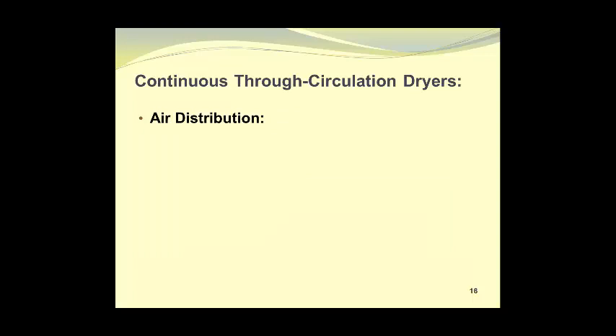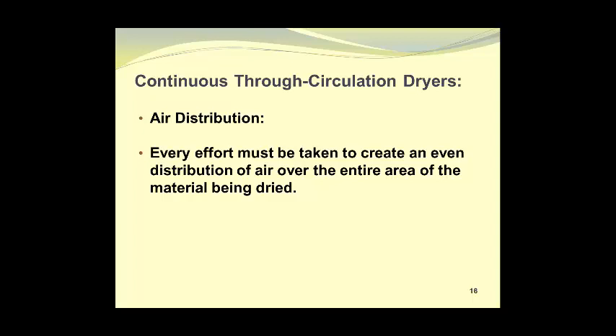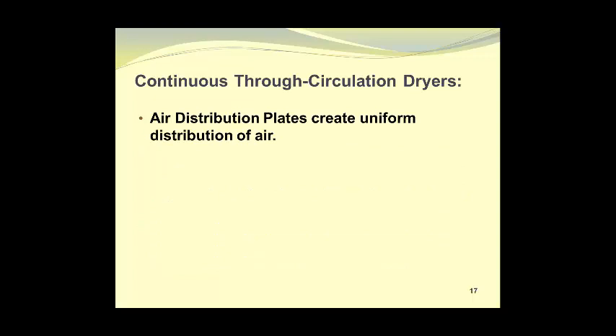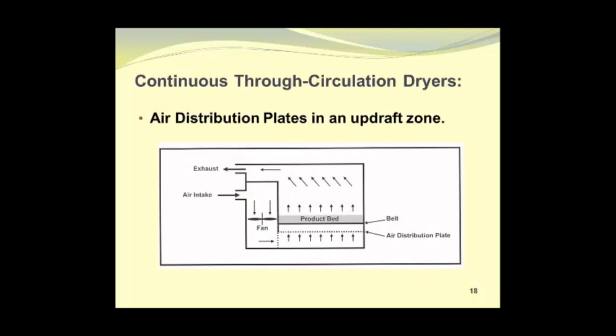Air distribution is an important factor. Every effort must be taken to create an even distribution of air over the entire area of the material being dried. Uneven distribution of air creates a lack of uniformity in the moisture of the dried product leaving the dryer. Air distribution plates create uniform distribution of air, as their name implies. Without them, air flow patterns are chaotic. Positioning of the distribution plates is quite important.